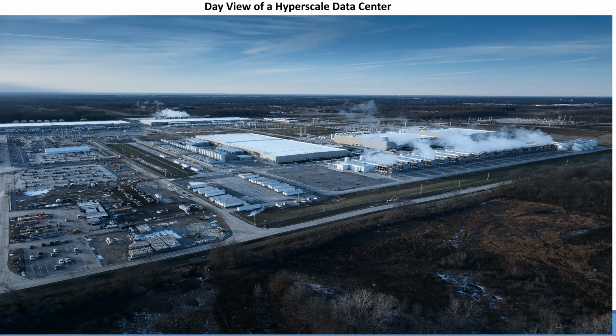And then the last chart I got of a building, this is one in Ohio. And the thing that I wanted to show on this one - if you look to the left, that's all construction area, what they've been building. And this project was built in 2 phases. They've got evaporative cooling - if you look on the right-hand side, you'll see towers that are emitting mist, that's evaporative. And if you get into an evaporative cooling situation, they use 1 million gallons a day for every 100 megawatt. So if you got a 500 megawatt facility, you're going to use 5 million gallons of water a day just to evaporate to remove the heat.